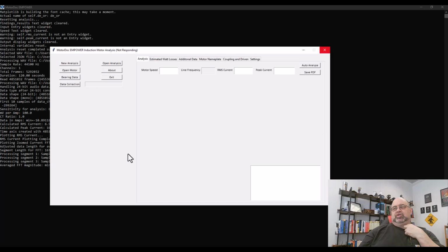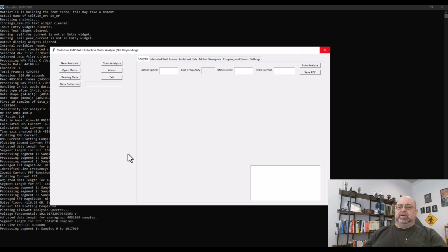Now, I'm assuming the machine is 2-pole, but we're going to take a look at this. I might have to adjust the nameplate a little bit. Could be at 1800 RPM, but there is no nameplate on that motor. Took the cover off, and there's not one inside either. I just know it's a 0.5 horsepower.